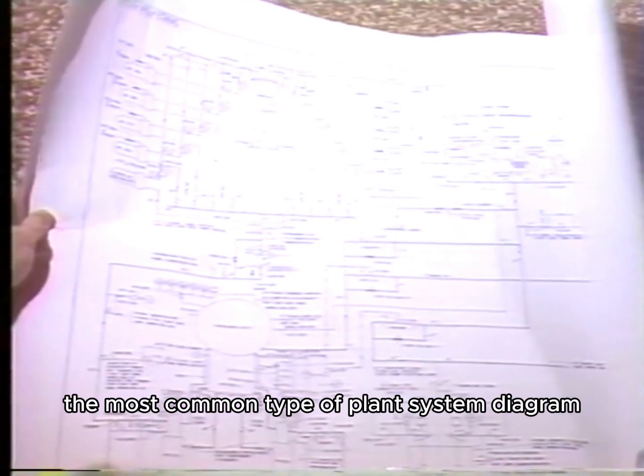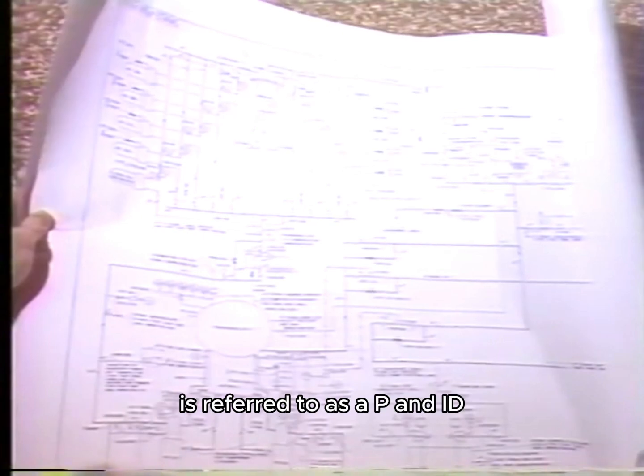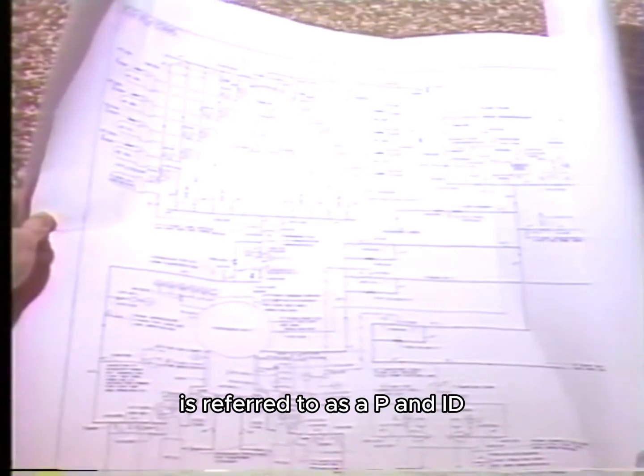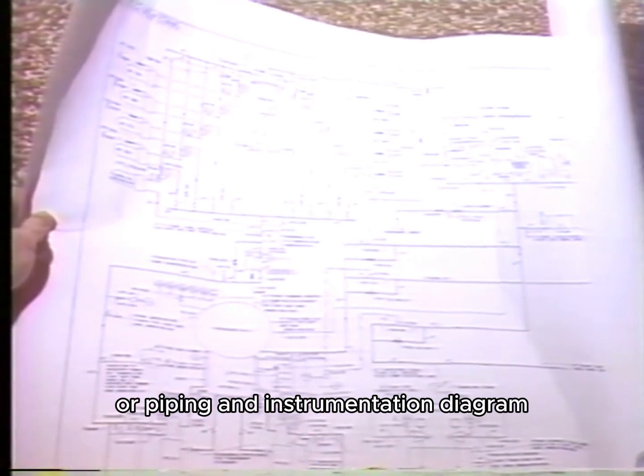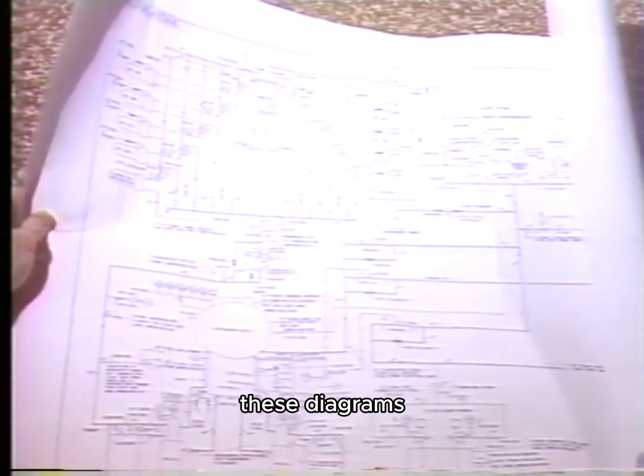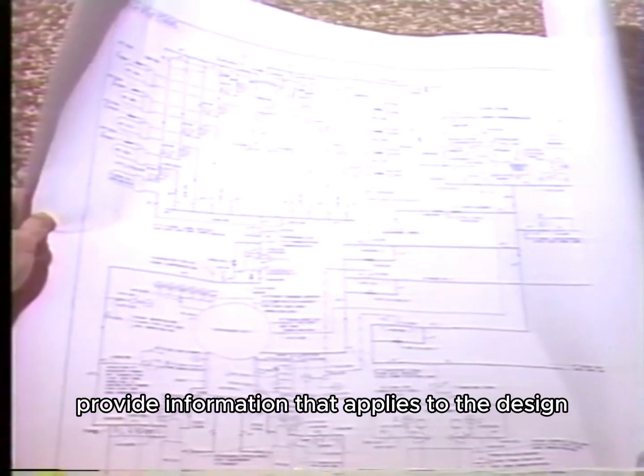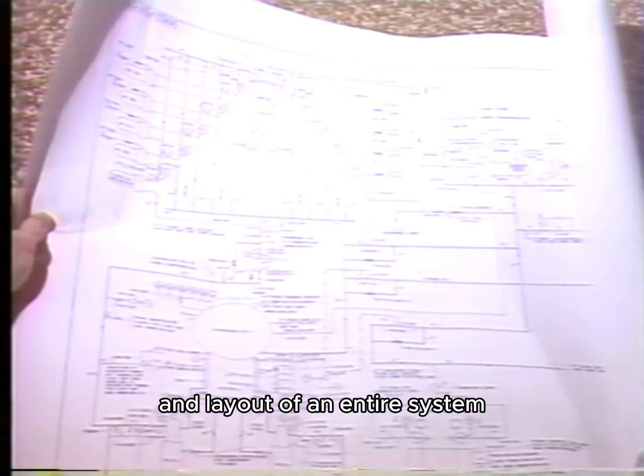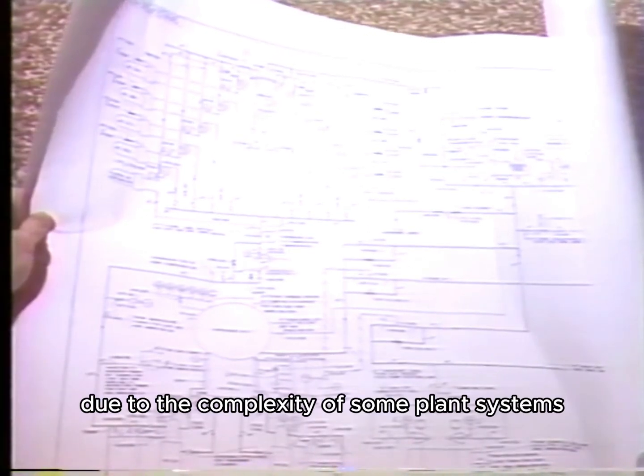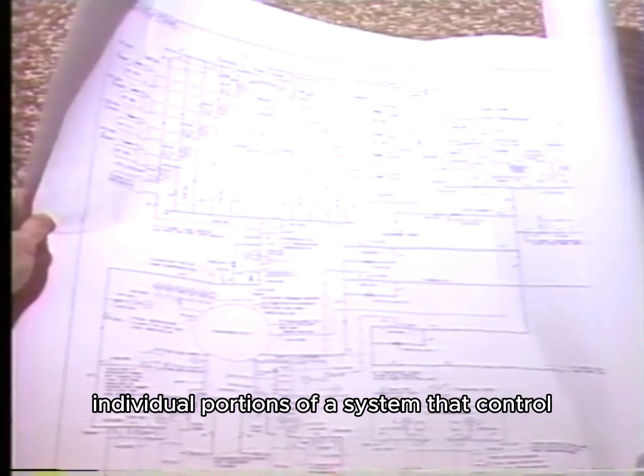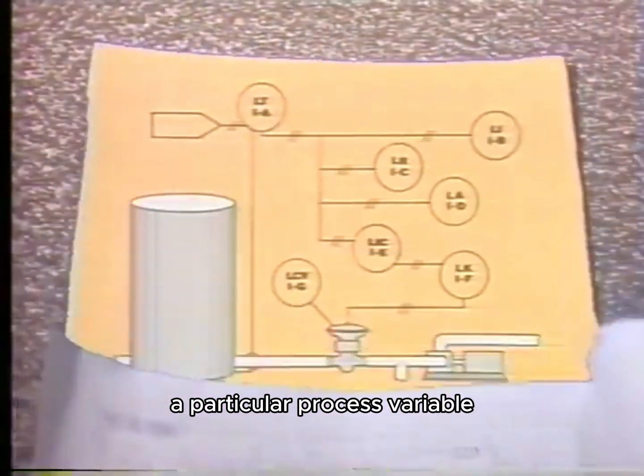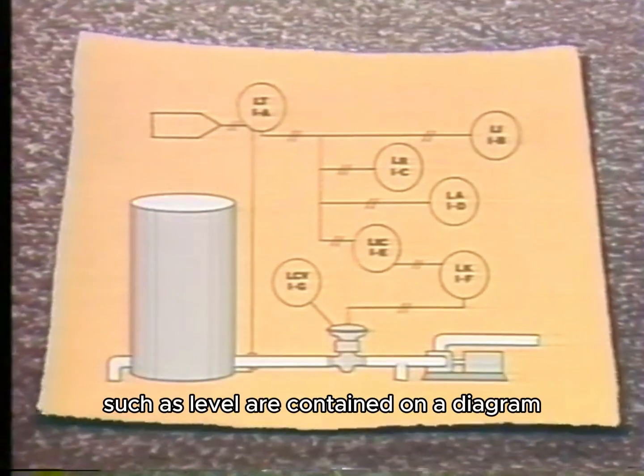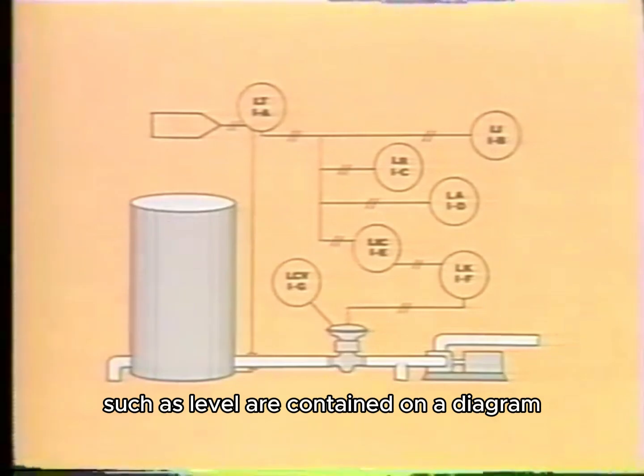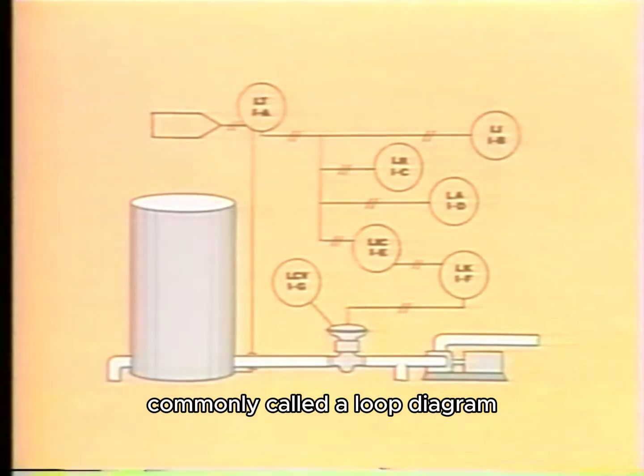The most common type of plant system diagram is referred to as a P&ID, or piping and instrumentation diagram. These diagrams provide information that applies to the design and layout of an entire system. Due to the complexity of some plant systems, individual portions of a system that control a particular process variable, such as level, are contained on a diagram commonly called a loop diagram.